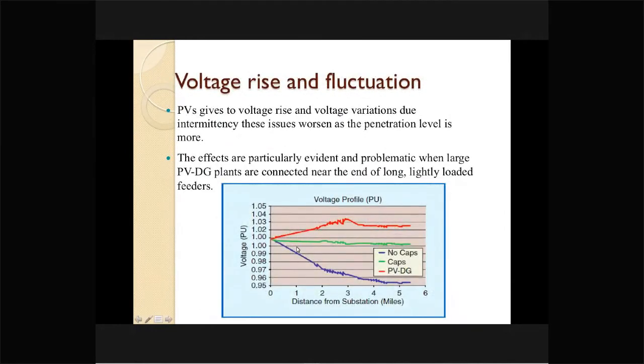A similar scenario will also occur with the voltage rise phenomenon. Generally speaking, the voltage in a feeder, when there is no photovoltaic or no DG integrated into the system, will go on falling as you go towards the last mile from the substation. So to make the profile better, we go for capacitor placement, and when we put in capacitors, it becomes more or less flat. However, when you go for photovoltaic integration, the PV system makes the voltage go on increasing.